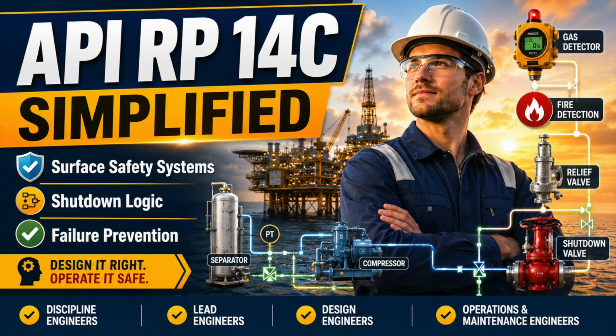Bypasses must be treated as temporary risk changes. Every bypass must be identified, time-limited, compensated, independently cleared, and visible to operations. A bypass is not merely a maintenance convenience. It is a deliberate degradation of protection.